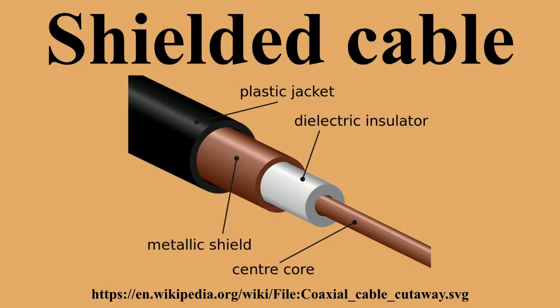Applications. The use of shielded cables in security systems provides some protection from power frequency and radio frequency interference, reducing the number of false alarms being generated. The best practice is to keep data or signal cables physically separated by at least 3 inches from heavy power circuits which are in parallel.